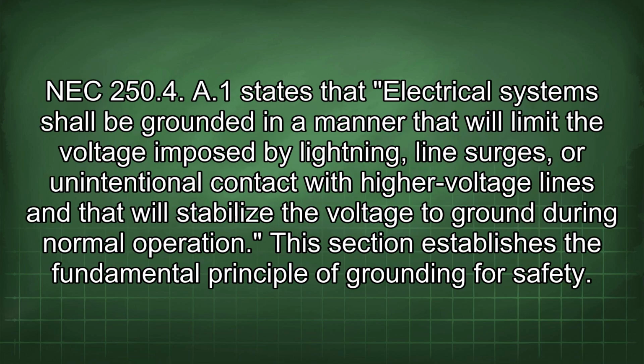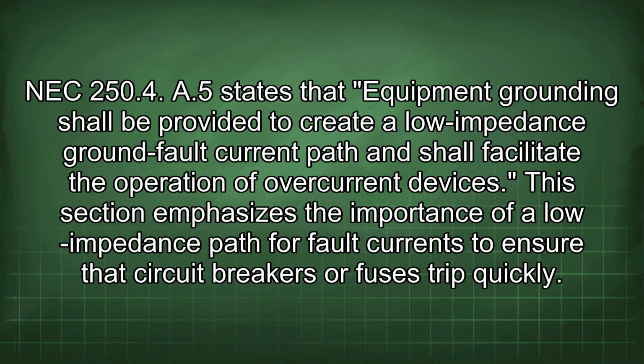NEC 250.4(A)(1) states that electrical systems shall be grounded in a manner that will limit the voltage imposed by lightning, line surges, or unintentional contact with higher voltage lines, and that will stabilize the voltage to ground during normal operation. This section establishes the fundamental principle of grounding for safety. NEC 250.4(A)(5) states that equipment grounding shall be provided to create a low impedance ground fault current path and shall facilitate the operation of overcurrent devices.